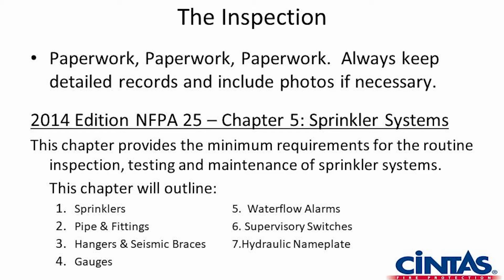Water flow. The water flow switch is a vane type, which has a nylon disc that is the same circumference as the pipe. It sits inside the pipe, and as water flows past it, it causes that nylon disc to raise. When it raises, it makes a contact point and closes the alarm circuit, which will then communicate with the fire alarm to central station to have the fire department dispatched.